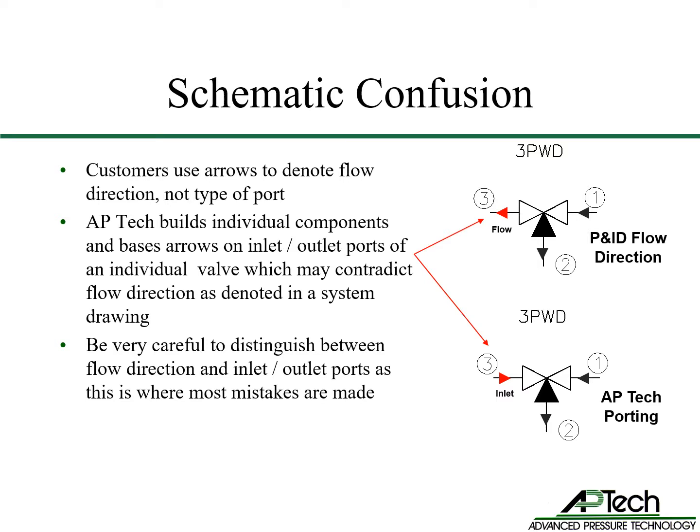A customer's piping system diagram may use arrows or triangles to indicate flow direction, not the type of valve port. Be very careful to distinguish between P&ID flow direction and AP Tech inlet and outlet ports, as this is where most mistakes are made. In the top diagram, a customer's P&ID indicates flow direction with arrows — gas flows through the valve under the seat from left to right and exits port number three. However, in the bottom diagram, AP Tech porting under the seat is always an inlet even if the flow direction of port number three is in fact reversed.